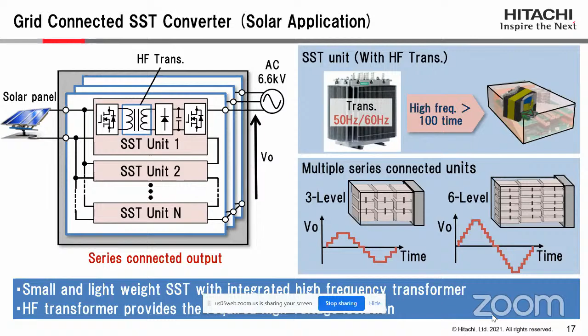Some of the critical challenges with this type of converter are hardware related. First, cooling system design. We need very efficient cooling, because there are multiple converter units installed in a very narrow area. So we need to take out the heat very efficiently, otherwise it will increase the temperature and it may blow any of the units. And we are placing both the converter and the high frequency transformer very close to each other, so the heat of the transformer can interfere with the heat of the converter unit and vice versa.